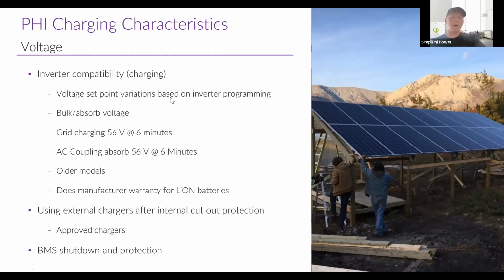So as far as inverter compatibility and charging, the voltage set points can vary a little bit based on your inverter. For example, for certain manufacturers, we may vary the bulk or absorb voltage by as little as 0.4 of a volt. So we do have integration guides on our website that show you the exact voltage to program everything to, depending on what equipment you have. Really, that 56 volts at 6 minutes is what we're going to go to with just about every manufacturer for the most part. There are a couple exceptions where we're varying that just a little bit.